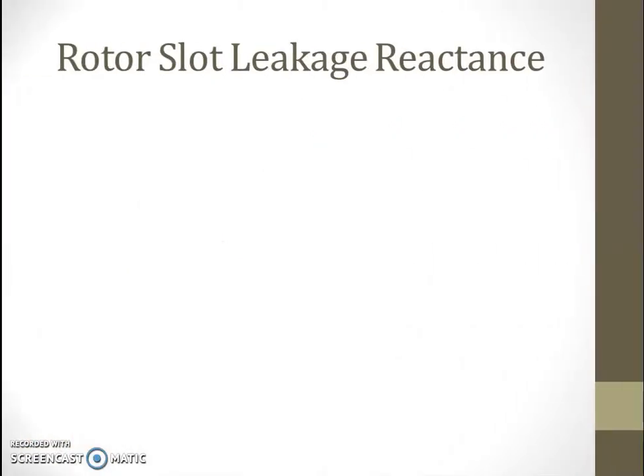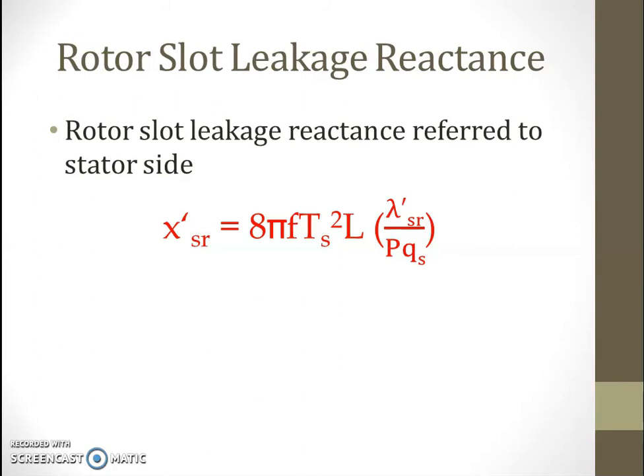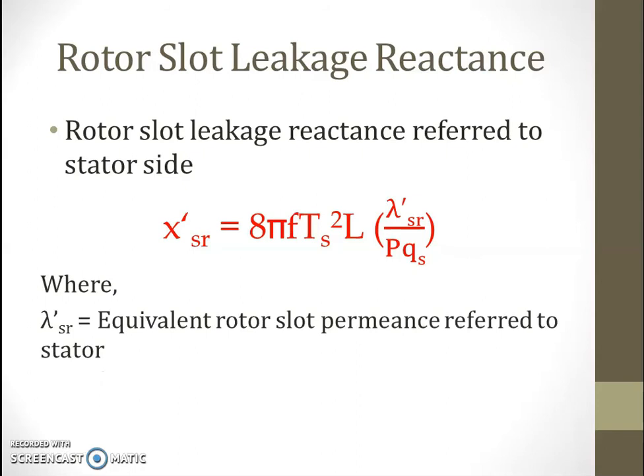Similarly, rotor slot leakage reactance referred to the stator side (denoted with a dash) has an almost similar equation: 8·pi·f·Ts²·L·lambda'_sr / (p·qs), where lambda'_sr is the equivalent rotor slot permeance referred to the stator, p is number of poles, and qs is number of stator slots per pole per phase.